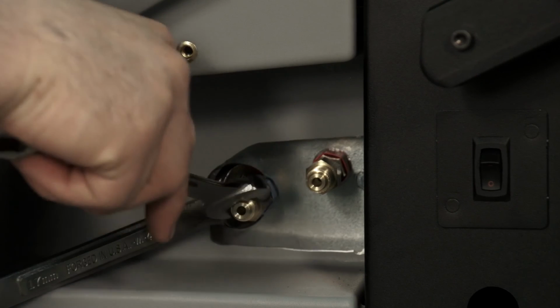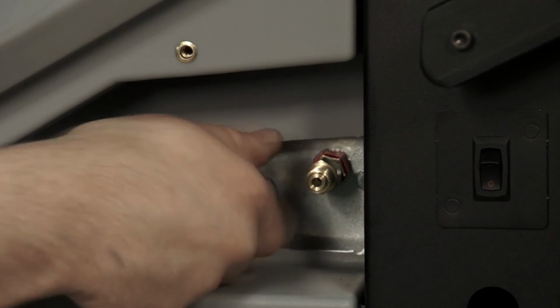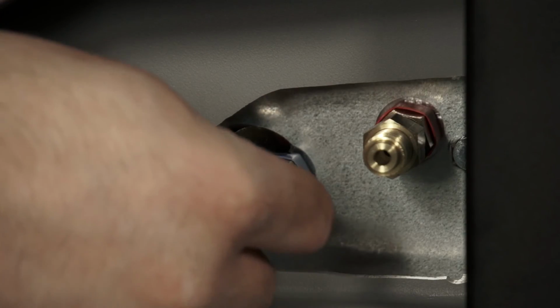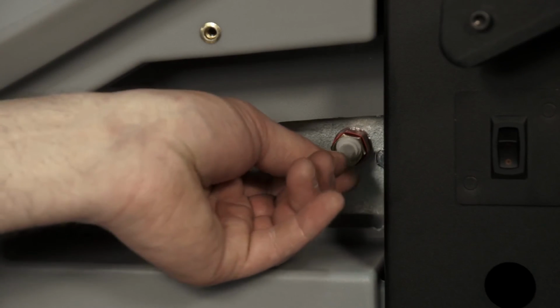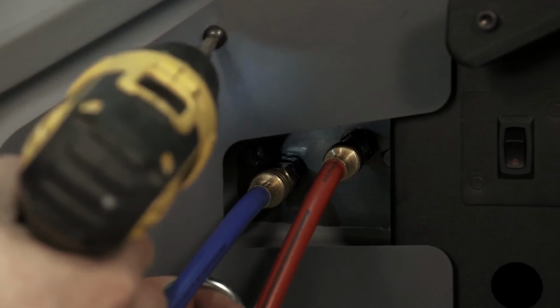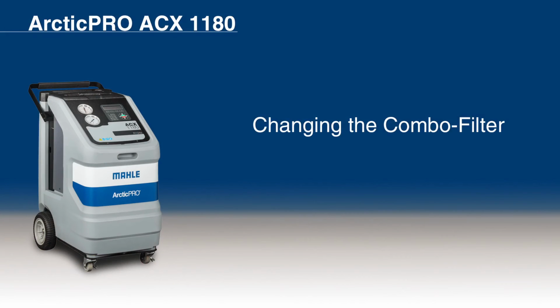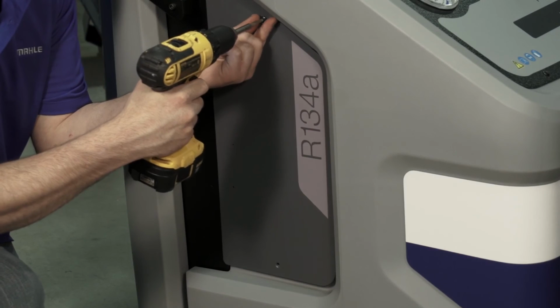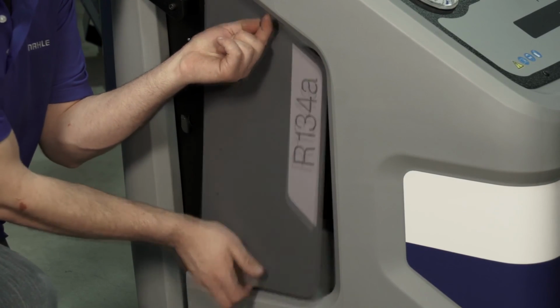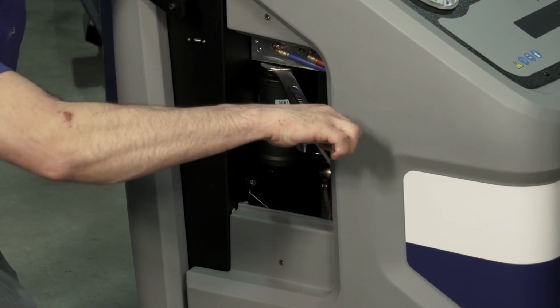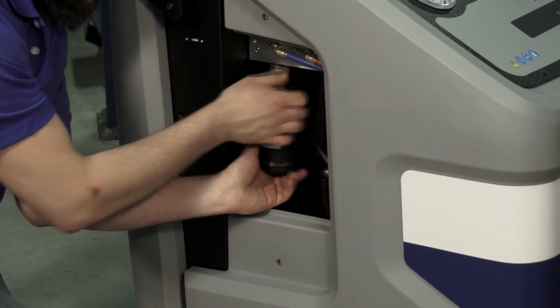Remove the filter element and replace with a new filter. Reconnect the service hoses and replace the panel. Changing the combo filter. The ACX1180 is disabled once 150 pounds of R134A refrigerant have passed through the filter. To install a new filter, drain the service hoses and remove the right access door. Loosen the filter using a 1 3/8 inch wrench. Finish removing the filter by hand.